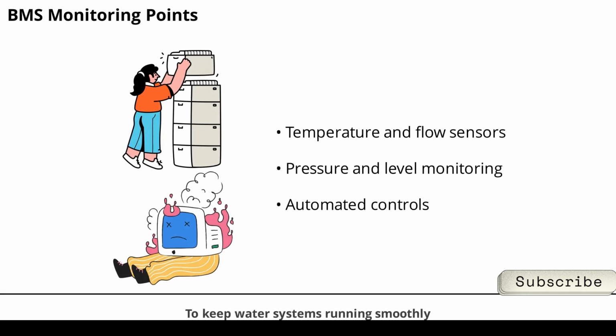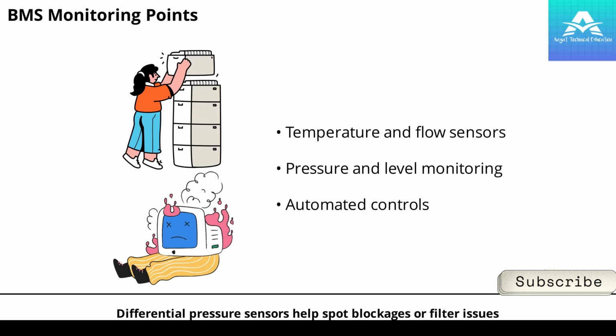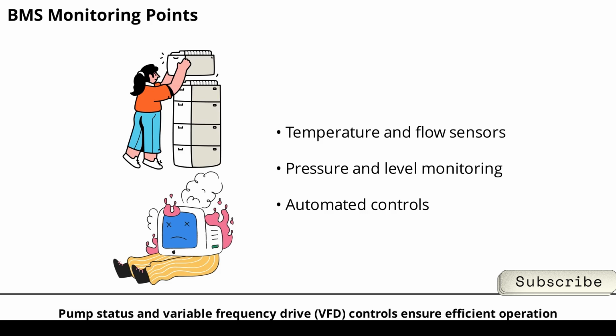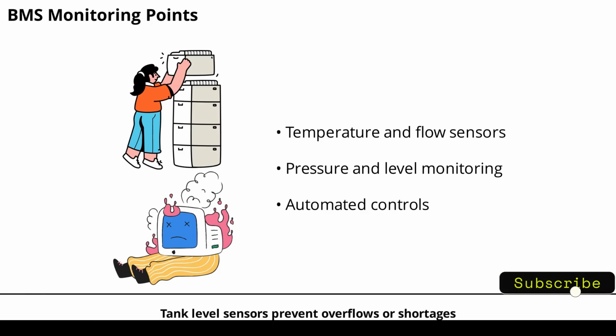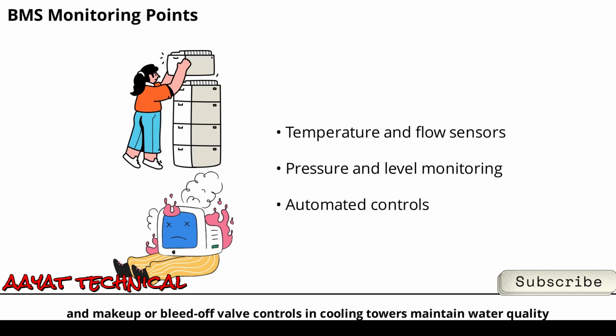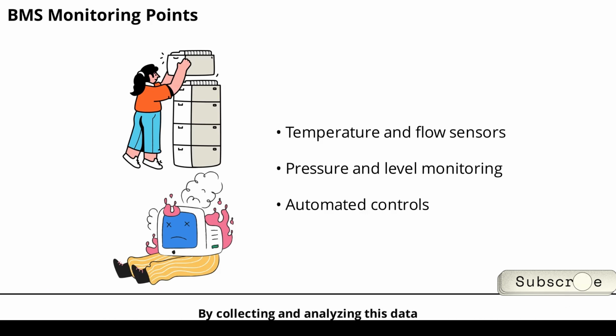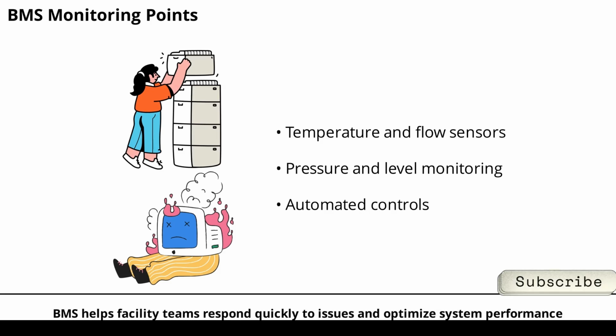To keep water systems running smoothly, BMS uses a range of sensors and controls. Inlet and outlet temperature sensors monitor system performance, while flow sensors and water meters track usage and detect anomalies. Differential pressure sensors help spot blockages or filter issues. Pump status and variable frequency drive, VFD, controls ensure efficient operation. Tank level sensors prevent overflows or shortages, and make-up or bleed-off valve controls in cooling towers maintain water quality. By collecting and analyzing this data, BMS helps facility teams respond quickly to issues and optimize system performance.